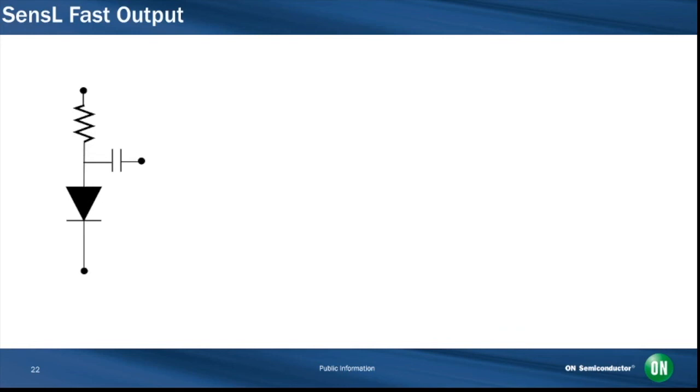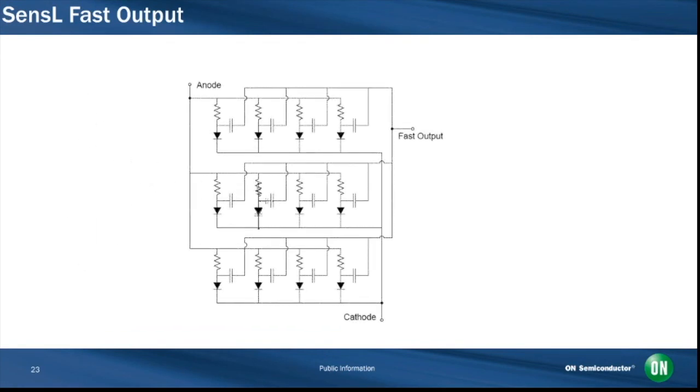The fast output signal is then the derivative of the internal fast switching of the microcell in response to the current flow from a detected photon. SensL SIPMs therefore have a third terminal for this fast output. And like the anode cathode output, it's formed from the sum of all microcells, so the pulse height is also proportional to the number of triggered microcells.